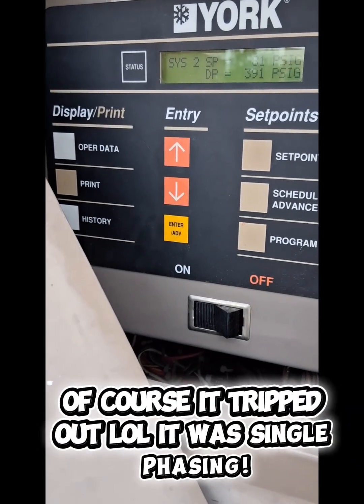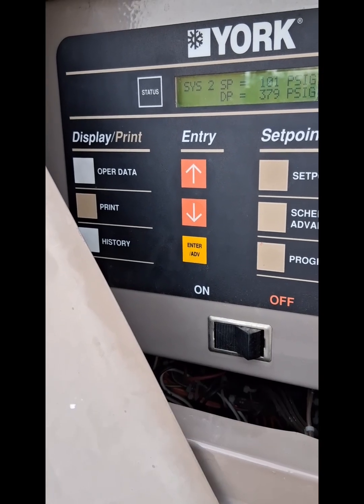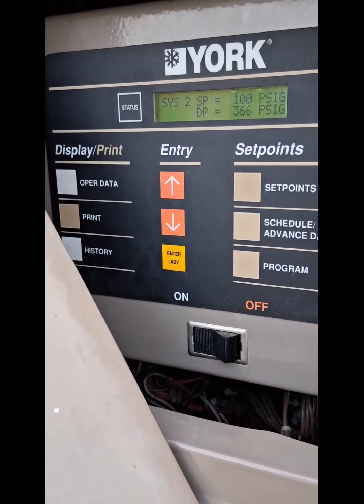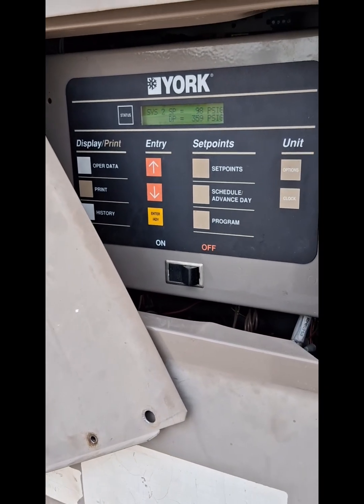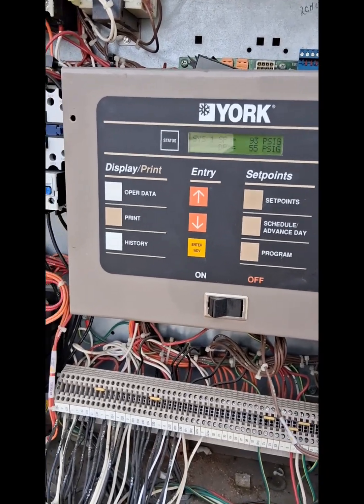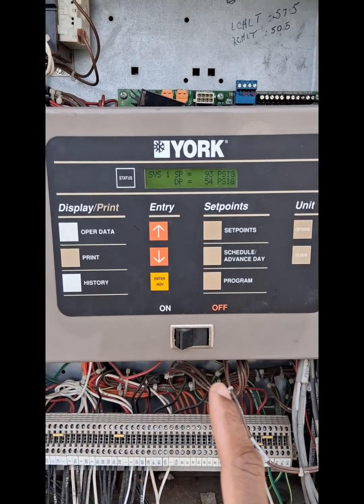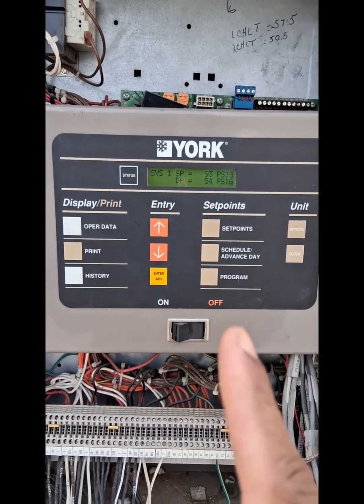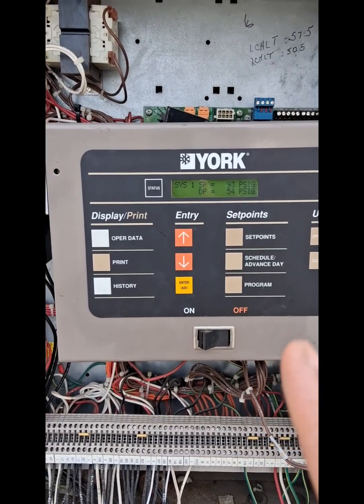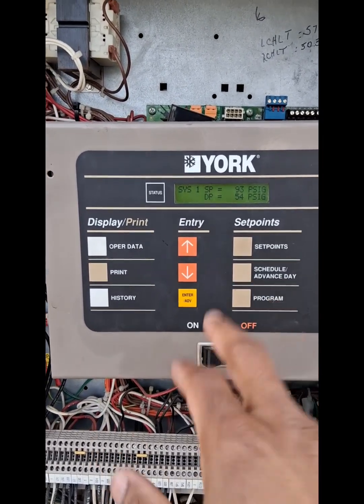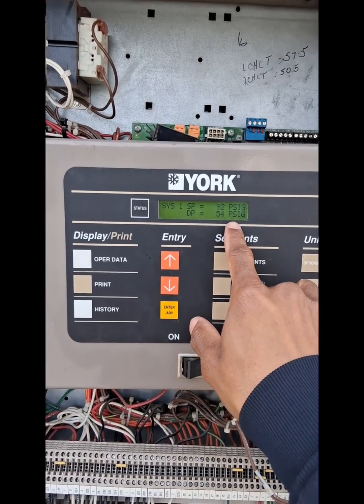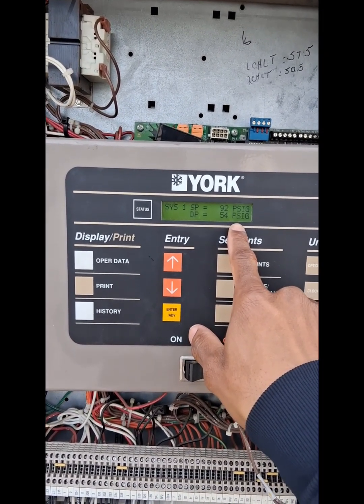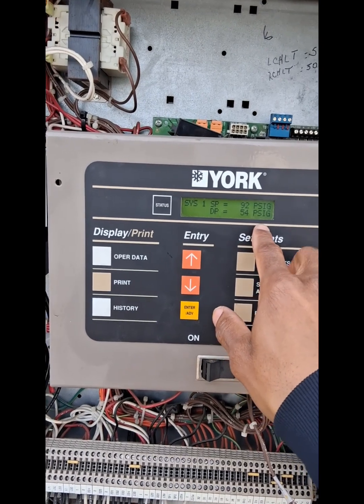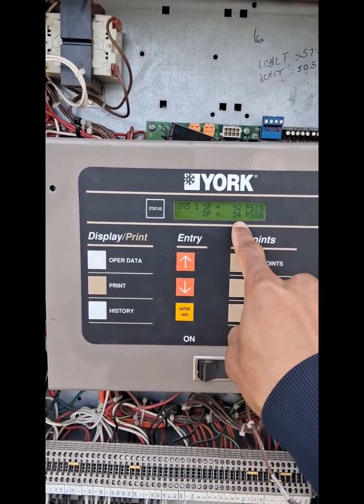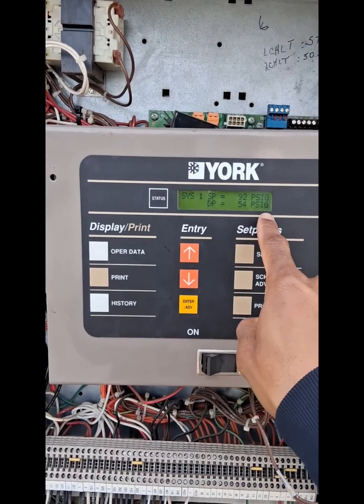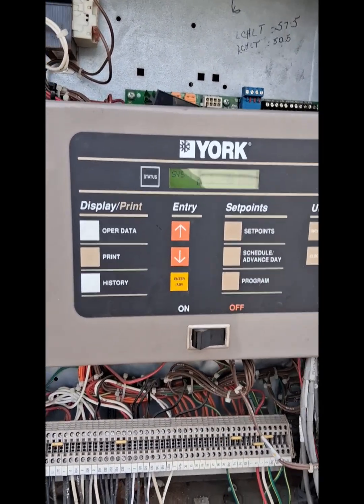Tripped out. Alright. Gotta figure something out to keep it online. So the problem I'm having on this chiller is circuit 2 has a bad fan motor, and it's tripping out on high head pressure. Circuit 1 has a bad discharge pressure switch, and it's not allowing the fan to come on. The unit is running extremely high head pressure, but this is not accurate, and I just heard the compressor making weird noises, so I shut it off.